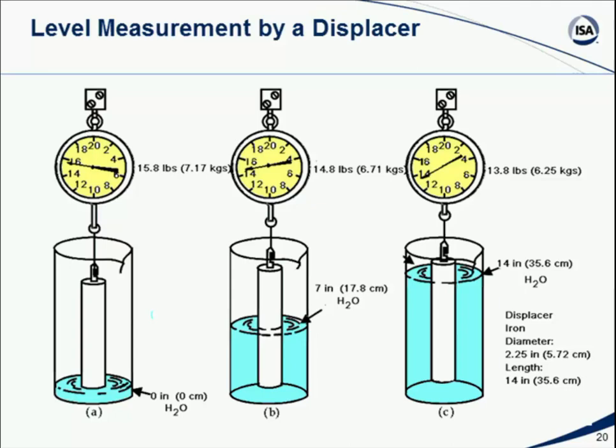Now, as the water level in the tank rises, more and more of the displacer is in the water, and it's displacing its own volume of water, and that water that's being displaced is pushing back against the displacer and essentially pushing it upward, and therefore making its hanging weight seem less and less.